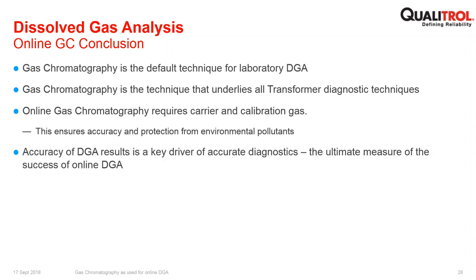Accuracy of dissolved gas analysis is a key driver of accurate diagnosis, and ultimately the reason that online dissolved gas analysis is put in place is not for measurement of ppms, it's not for rate of change, it's not for trending purposes, it's for transformer diagnostics. If you want to perform accurate transformer diagnostics, you need accurate data. And for all of the reasons shown in the presentation, you get accurate data from gas chromatography.